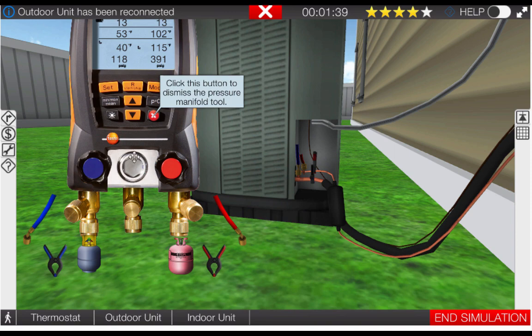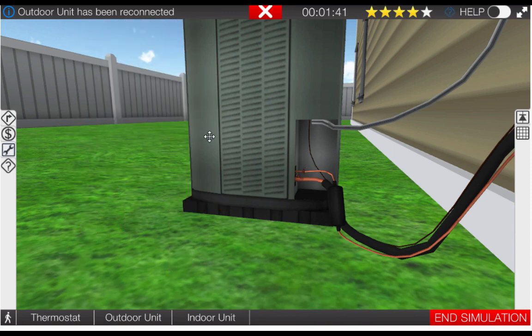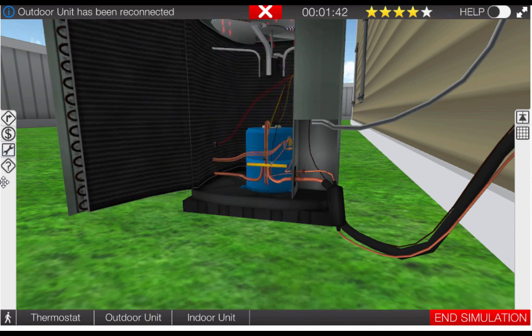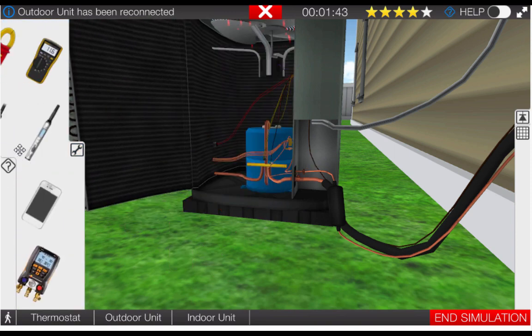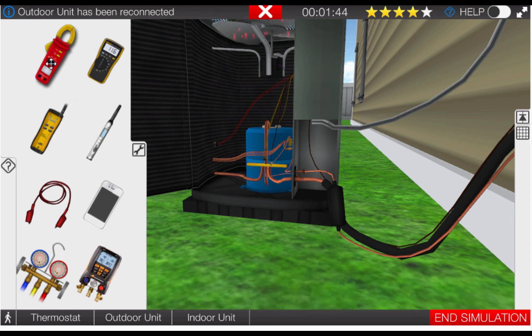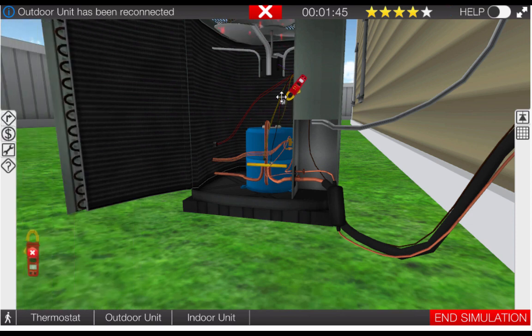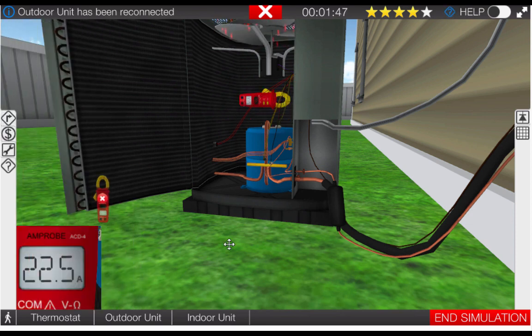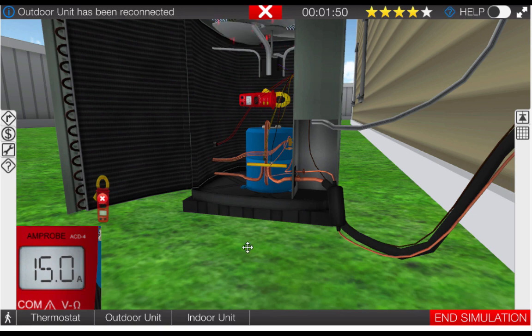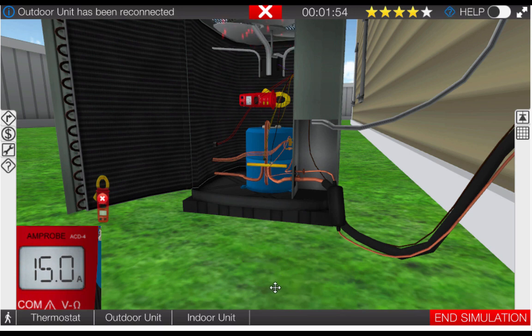Last but not least let's store the gauges away and check the compressor amperage. Placing the jaws of the clamp on around the glowing hot spot we can see that our amperage is now operating normally at 15 amps. So the problem's been corrected.